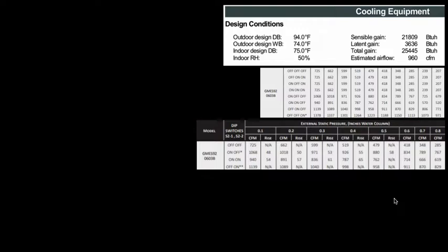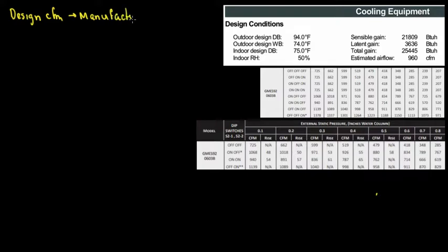So what we're going to do is calculate the cooling CFM. We call this the target CFM. And when we choose the CFM from the manufacturer, we call it design CFM. So design CFM comes from the manufacturer's blower data.